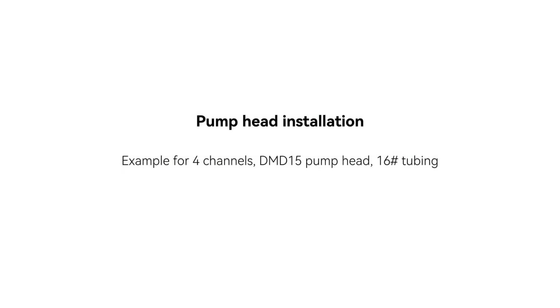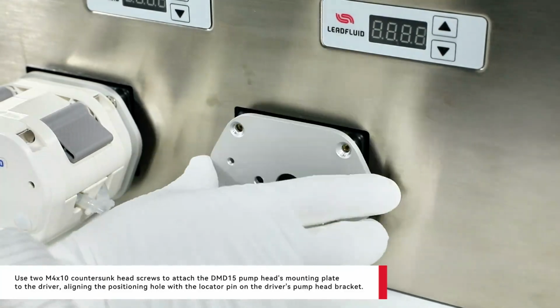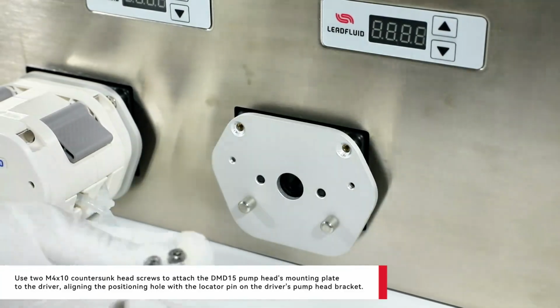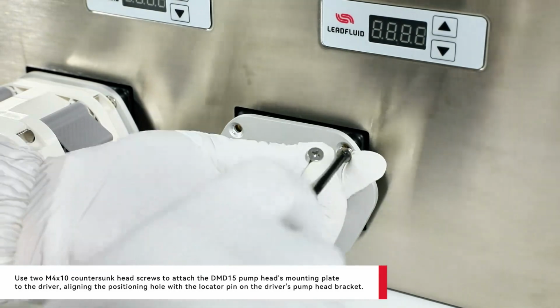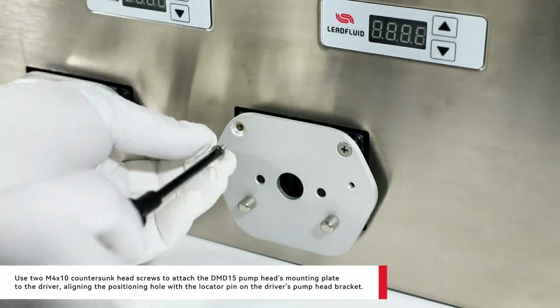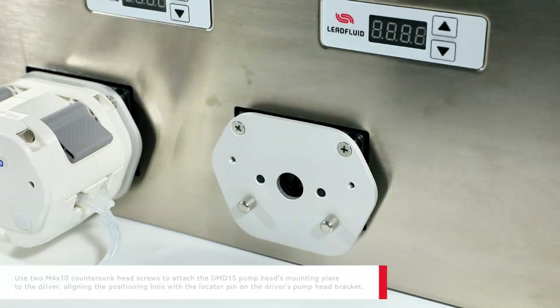Pump head installation, example for 4 channels, DMD15 pump head, 16 tubing. Use two M4X10 countersunk head screws to attach the DMD15 pump head's mounting plate to the driver, aligning the positioning hole with the locator pin on the driver's pump head bracket.